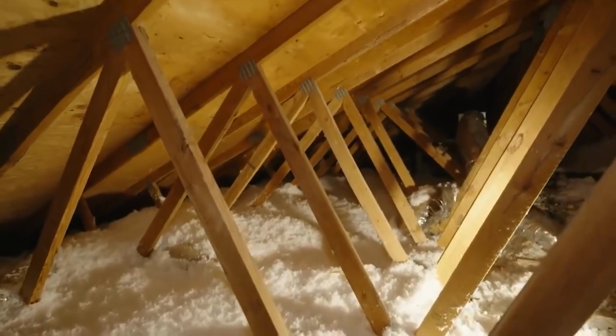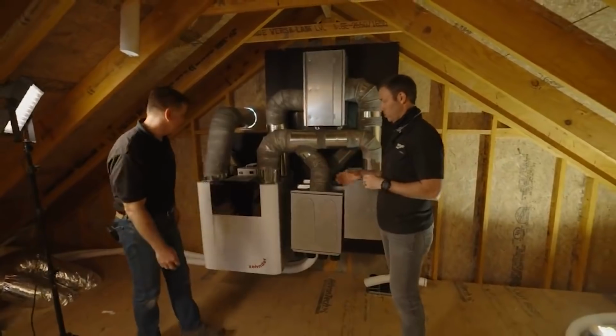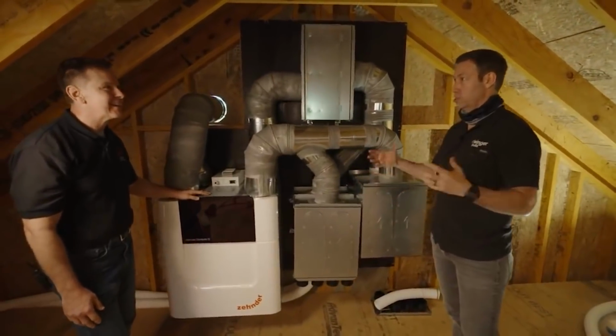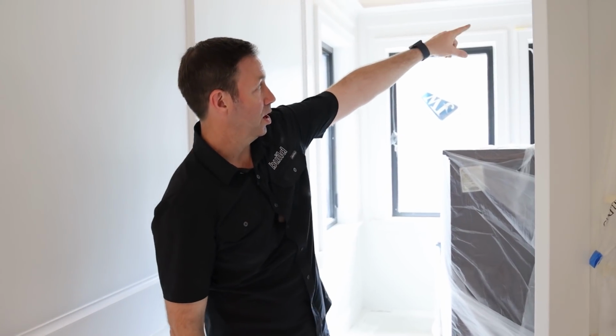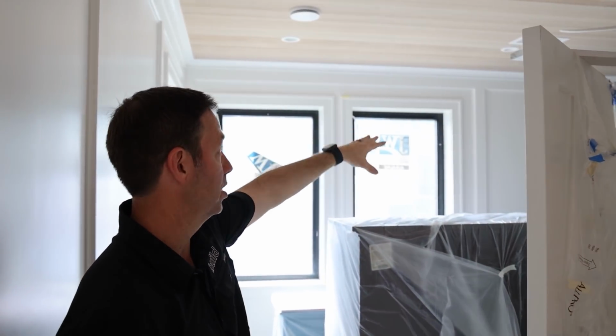What we're doing is making sure that air doesn't travel back up there. If you have a traditionally built house with insulation up in the attic, you're trying to make sure you don't get any airflow, any communication between your attic and your house. Now my HVAC equipment in my attic is all part of the air conditioned envelope, so I'm not as worried about that, but I do want to reduce sound transmission between kids' bedrooms, let's say, and I also want to make sure that if I've designed this system to put a certain number of CFMs out of that grill over there, that I'm getting that certain number of CFMs out.